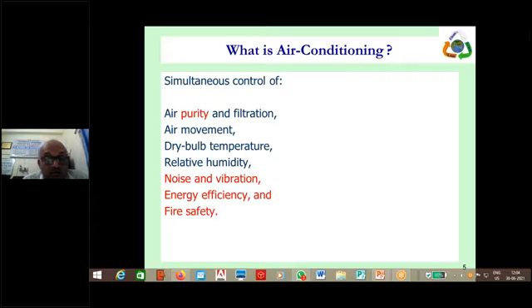Now again, before that, of course, we all know that air conditioning is mainly for comfort as well as for process purposes. So when it is for process purposes, the approach is different. When it is for comfort condition, then the approach is different. So air movement may be more if the process requires. Then dry bulb temperature we have to maintain within the comfort zone. Then relative humidity also, there are studies now available that how the combination of relative humidity and dry bulb actually can save energy. So by appropriately setting as per those conditions, we can save energy. Noise and vibration is also included, because if the air conditioning is creating noise or vibration, again it is putting into a different form of discomfort. So noise and vibration also included.